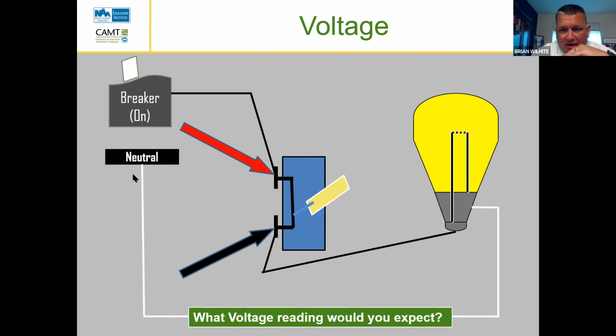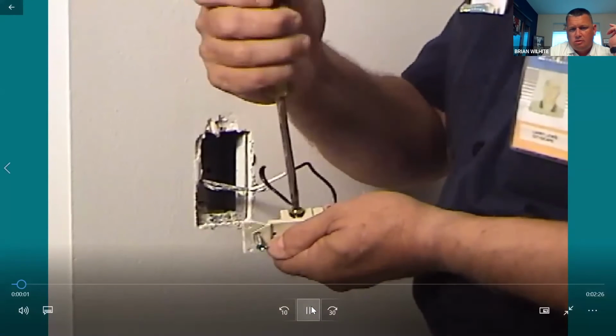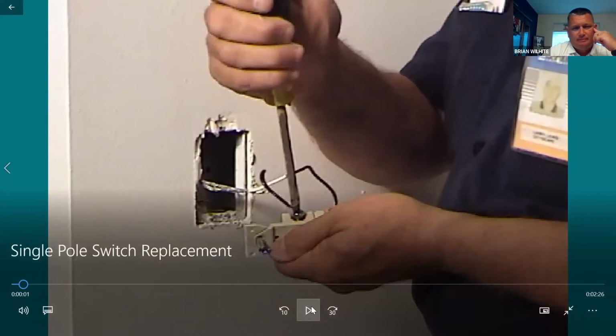And our meter, if we remember back to the beginning of our teaching today, reads the difference. And so right now with our switch closed, there is no difference between the black line coming into our switch and the black line leaving our switch, because it's all the same 120 volts. And so as it sits right now, because there's no difference, we're going to read 0. Does that make sense? Yeah. At this point, you see now? Yep.